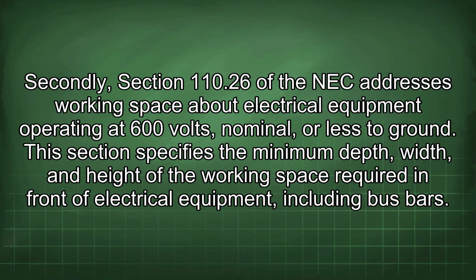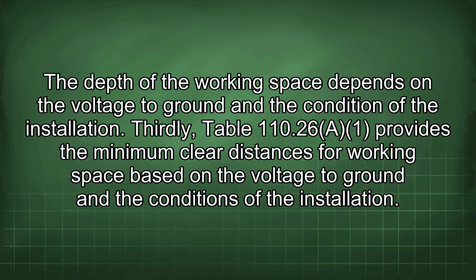This section specifies the minimum depth, width, and height of the working space required in front of electrical equipment, including bus bars. The depth of the working space depends on the voltage to ground and the condition of the installation.